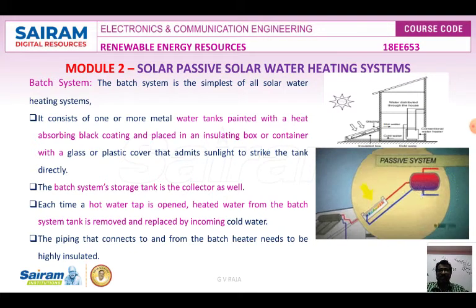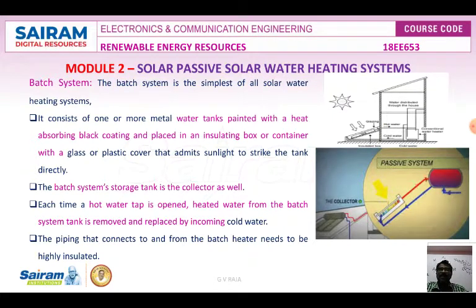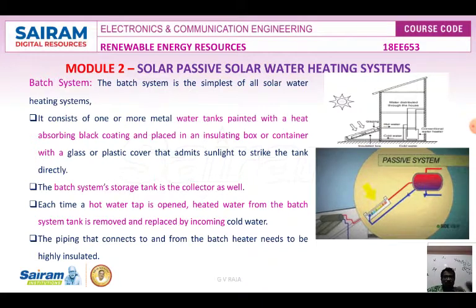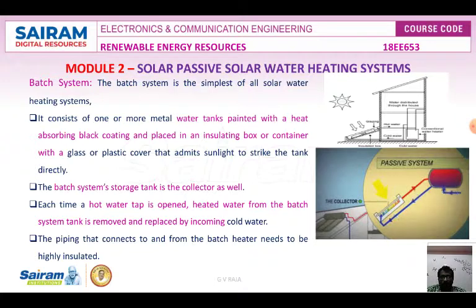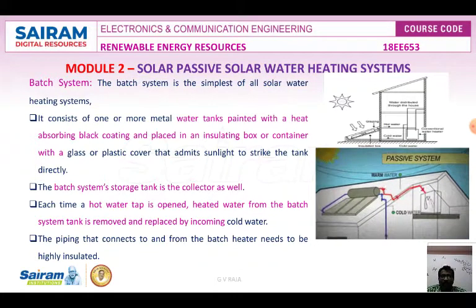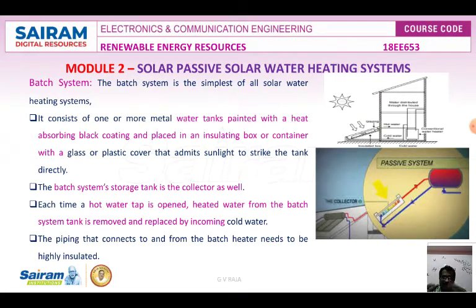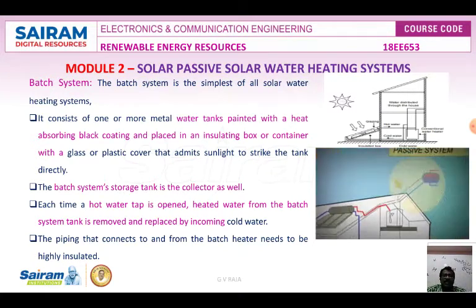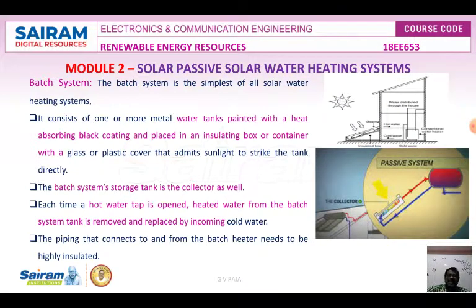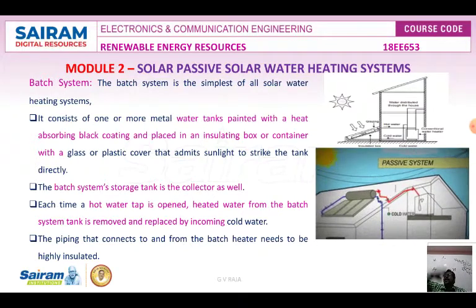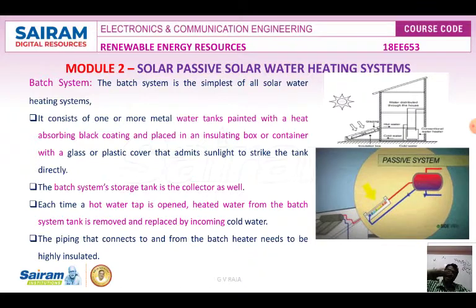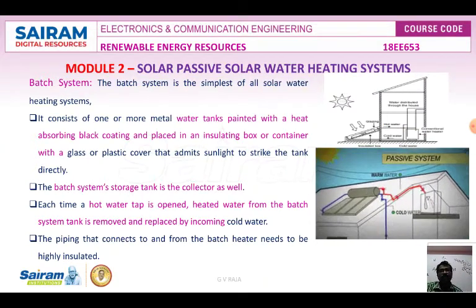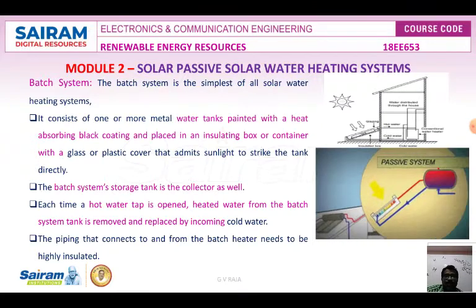There are two types of passive water heating systems: the batch system and the thermosyphon system. The batch system is the simplest of all solar water heating systems. It consists of one or more metal water tanks painted with a heat-absorbing black coating and placed in an insulated box or container with a glass or plastic cover that admits sunlight to strike the tank directly. Above the solar panel, there is a tank coated with black paint — that is the batch storage system.